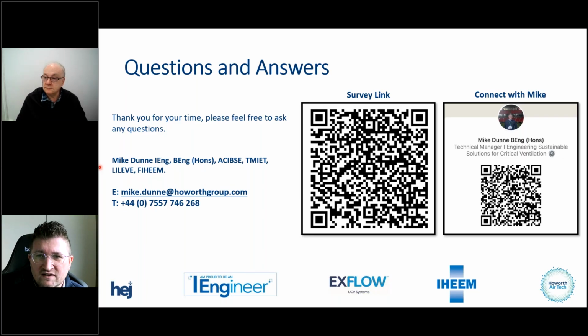But then I think it's the validator's responsibility to put a scope of works together that says at validation we are going to do this many variations of testing. And it is a lot of testing when you do a barn. If it's a four UCV barn, it is tons of testing, because you have to test in the different scenarios. So let's call it pod 1, 2, 3, 4. We switch pod 1 off, we test 2, 3, 4, and it's grids and entrainment. We bring pod 1 back on, switch pod 2 off, and test 1, 3, 4, grids and entrainment. It's a lot of extra work and a lot of extra testing.